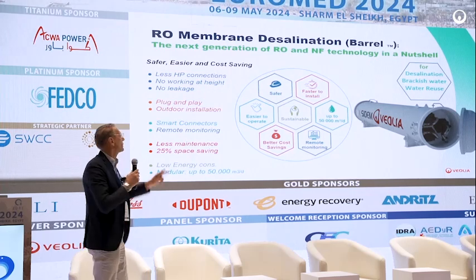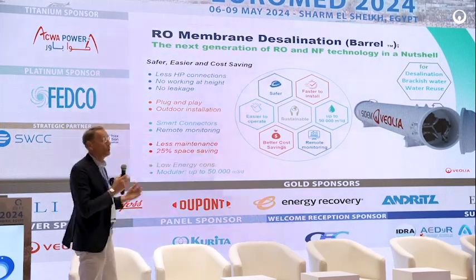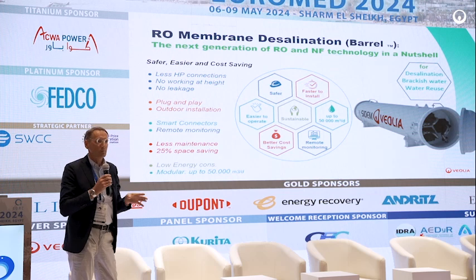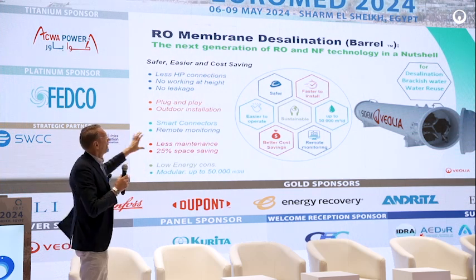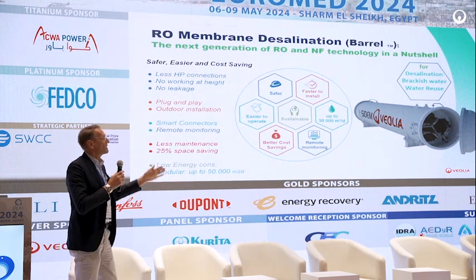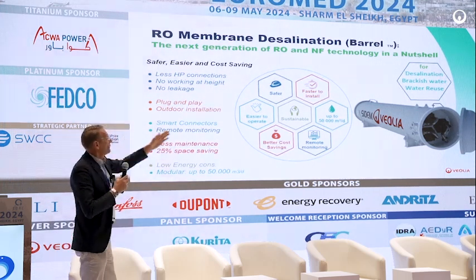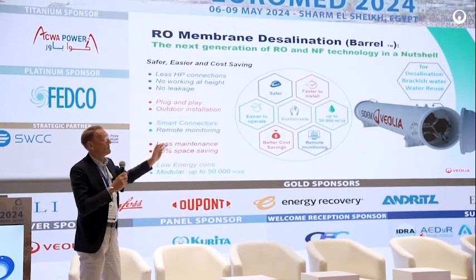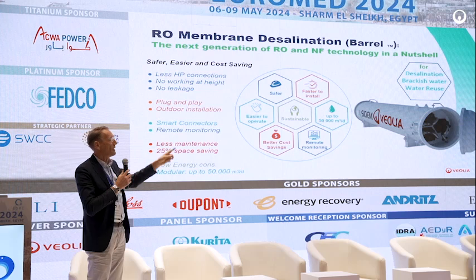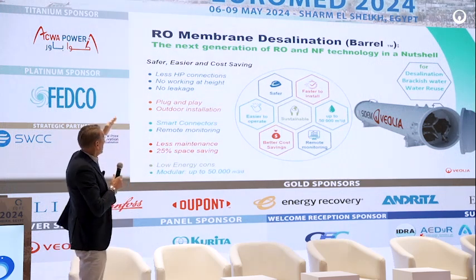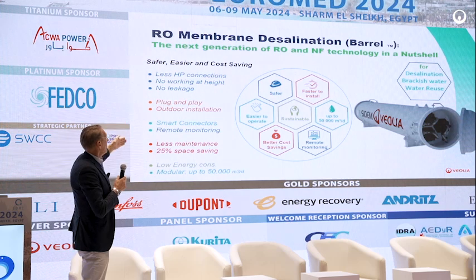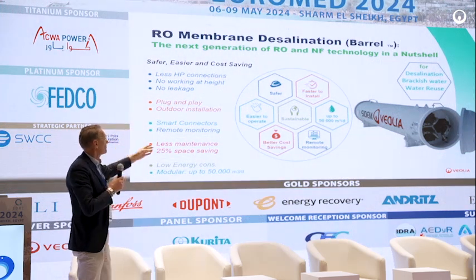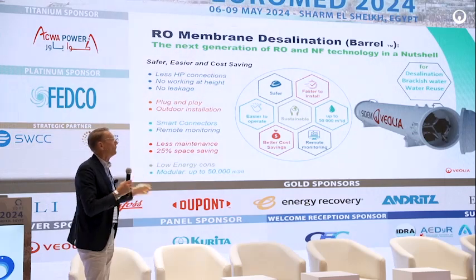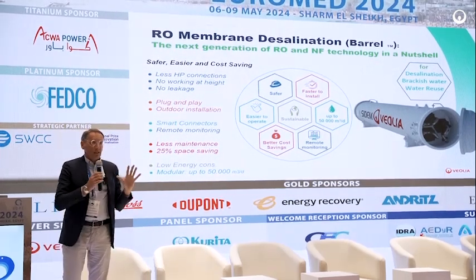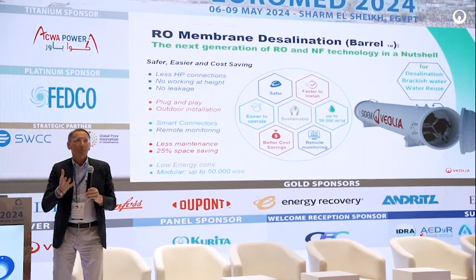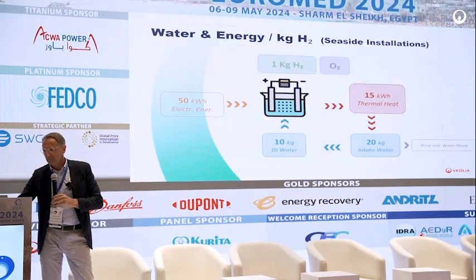On Tuesday we have the presentation of this new RO membrane desalination system that we patented, called the barrel. It's a new patented solution. As you can see, we try to reduce as much as possible the service and safety requirements with this system that includes everything. We dramatically reduce the number of high-pressure connections. We have a plug-and-play outdoor installation, less maintenance, 25% space saving, and it's modular up to 50,000 cubic meters per day. That is our approach to standard systems.